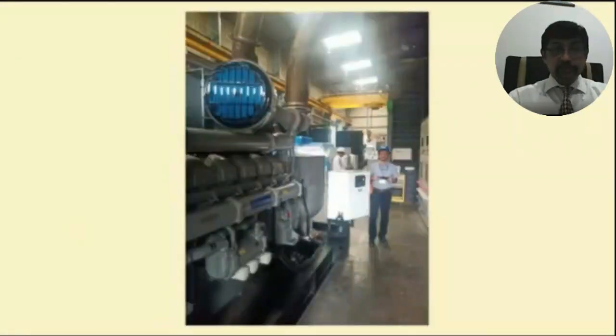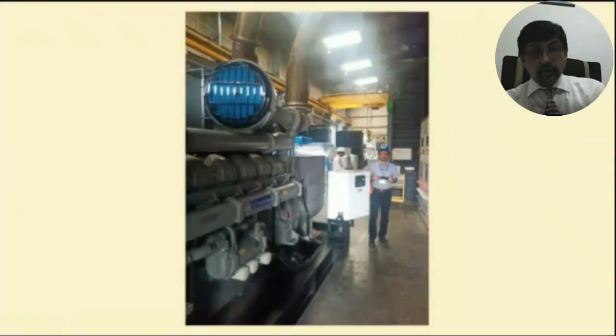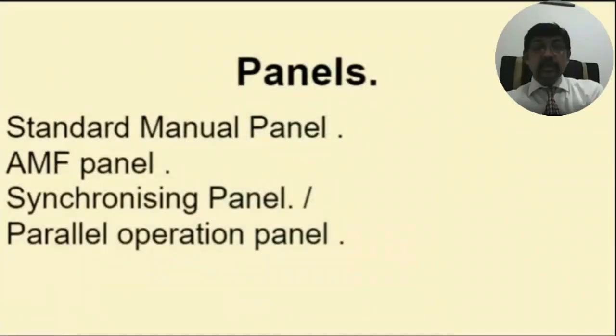Next, this is the generator, what we were talking about. The base frame we can see. Now the panels. The panels are of three types. First, of course, the standard manual panel. It is similar to a generator starting. When we start the generator, we have a standard manual panel to control and monitor the generator. But in case somebody wants, industries, hotels or malls now go for an automatic mains failure panel, that is an AMF panel.